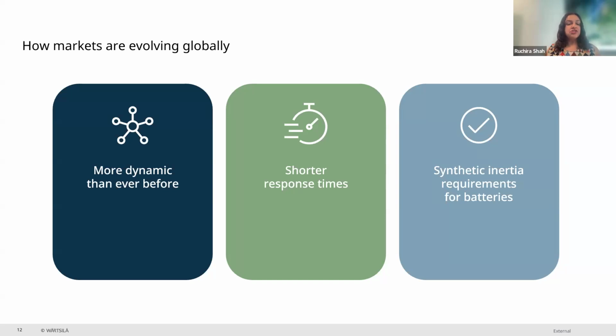Another really interesting thing we're seeing globally is increased synthetic inertia requirements for batteries. Synthetic inertia is a really interesting topic, but essentially inertia has been traditionally performed by conventional generation, like synchronous inertia. It was conventionally seen that inverter-based resources like batteries could not provide inertia to the grid.